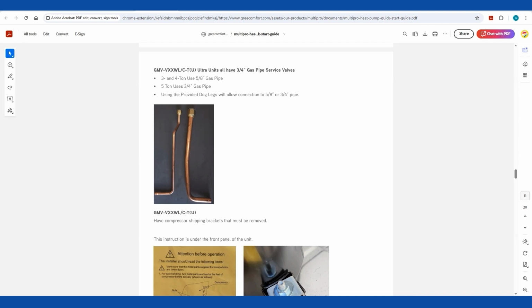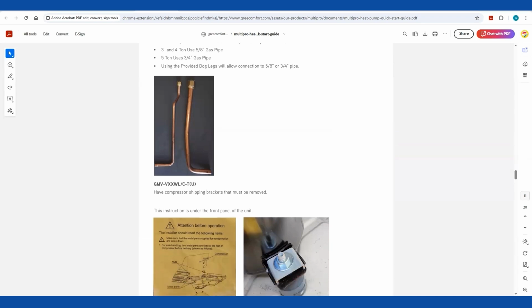However you guys want to do it, just keep in mind that the service valves themselves are going to take a 3/4 gas pipe, not 5/8. 5 ton is the only one that's going to use the 3/4. So just kind of an FYI.